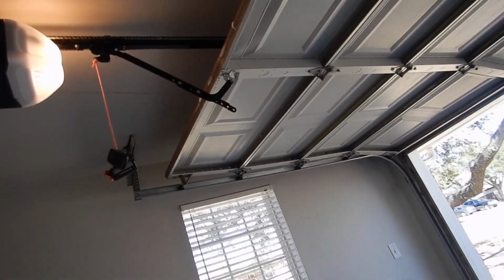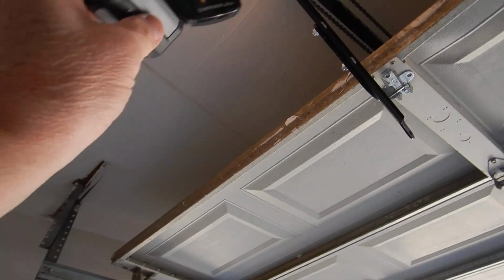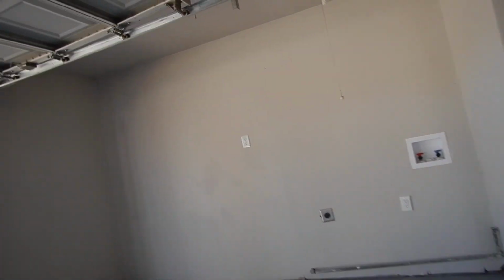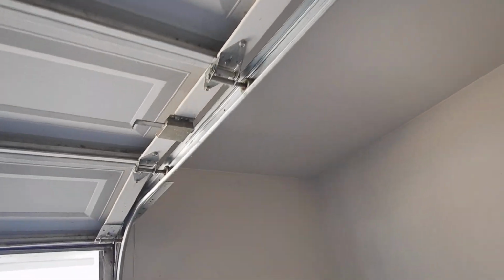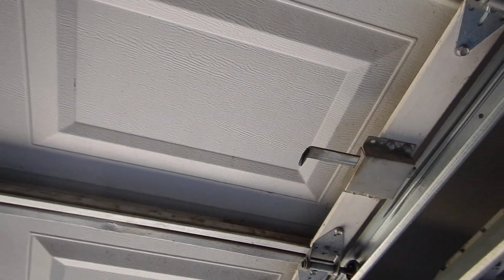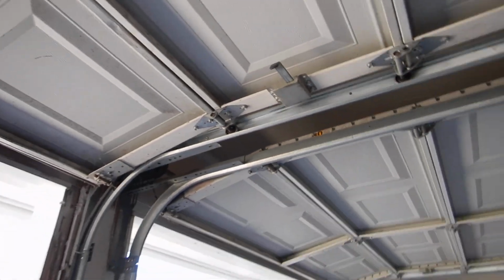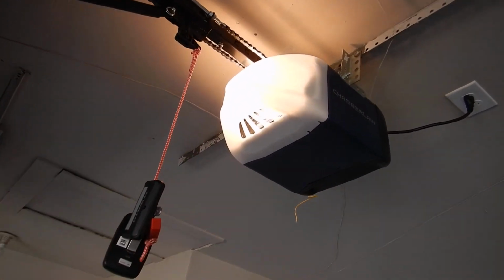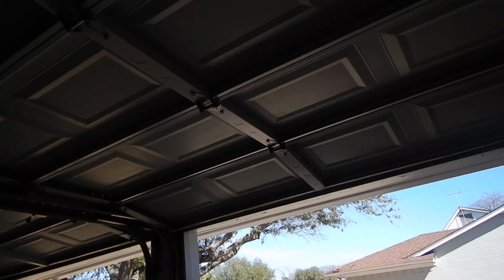We have our courtesy lights. We have our emergency pull handles coming on down. Our manual door locks have not been decommissioned. You could close the door, lock the door, forget that you locked the door, try to open the door again. The lock will keep the door from opening because that's its job. The motor will keep trying to open the door because that's its job. And the door will bend and flex and become distorted. Jacked up, man.